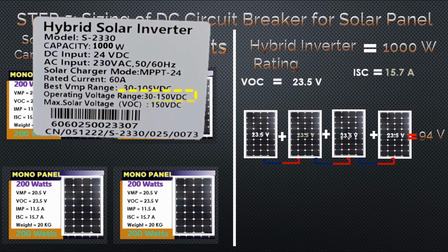So to compute for the rating of the circuit breaker, you will add to the value of ISC a 25% safety factor as per Philippine Electrical Code. So what is the 25% safety factor used for? This is the capacity that you will add to the rating of the circuit breaker to compensate for the continuous loads, because the operation in continuous loads should not exceed 80% of the circuit breaker's rating.